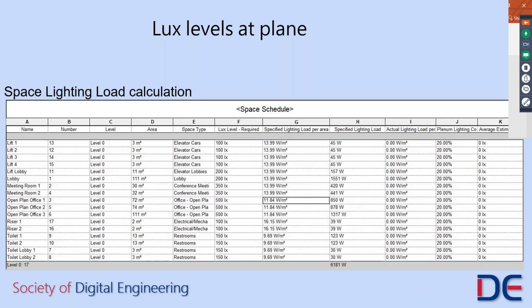We can then again create a space schedule. As we can see here, we have brought in our required lux levels. We have specified lighting load per area as a watts per meter squared value, and this is multiplied by the area of that space to give us an early indication of what the lighting load is going to be. And again, we can calculate the totals and look at what that value may be. We'll notice also that the actual lighting load and average estimated illumination are at zero because we haven't put any luminaires in the space yet.